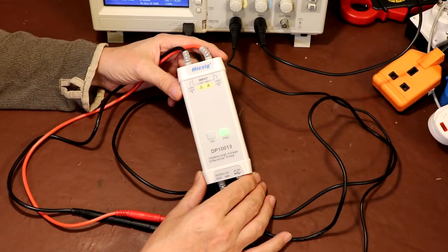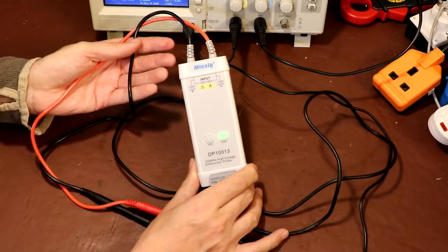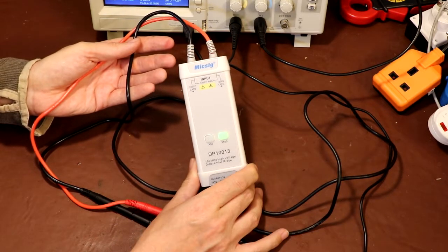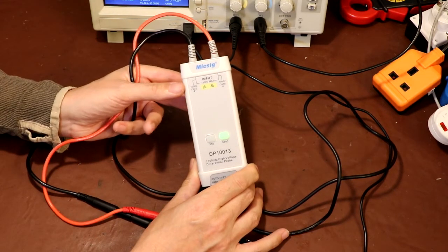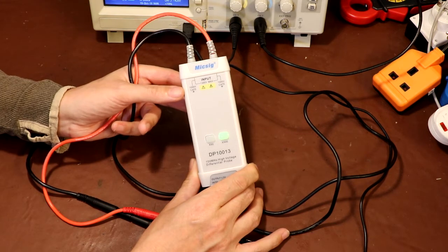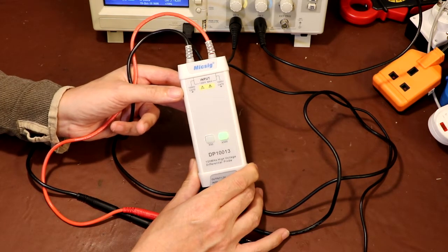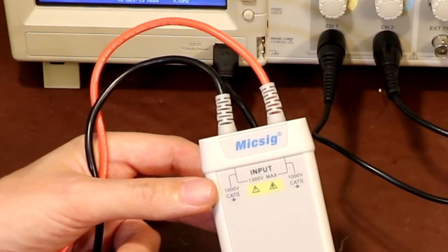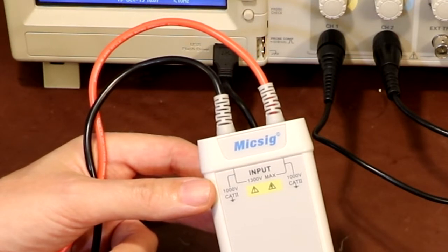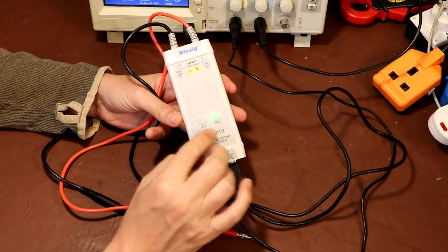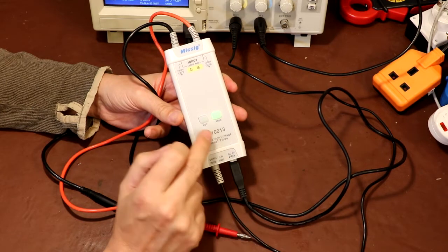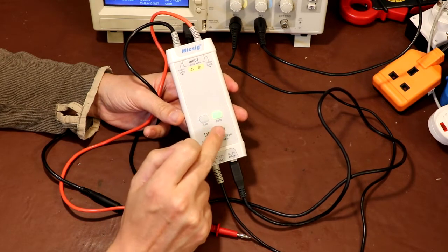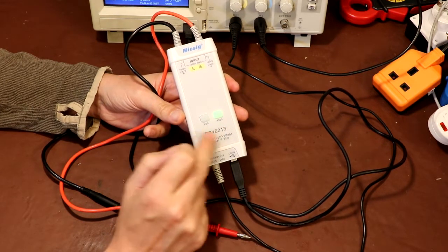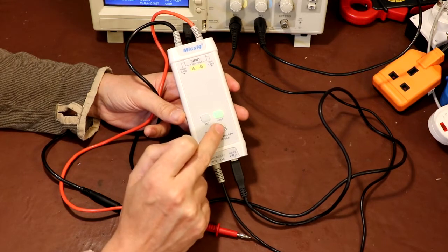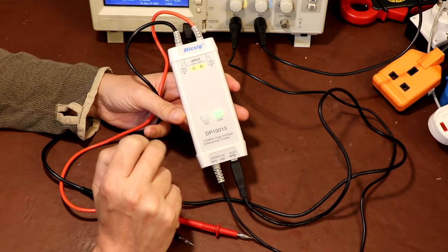So this is the differential probe that I'm going to be using today, which is manufactured by Micsig. At the top of the probe we've got the high voltage connections, and it also has the voltage specification on it. It says that it's a category 2 device, and we can use this probe up to 1300 volts maximum. Lower down on the unit we've got an attenuation factor where we can set it to times 50 or times 500, which is effectively dividing by that amount. At the moment I've got it set to 500.